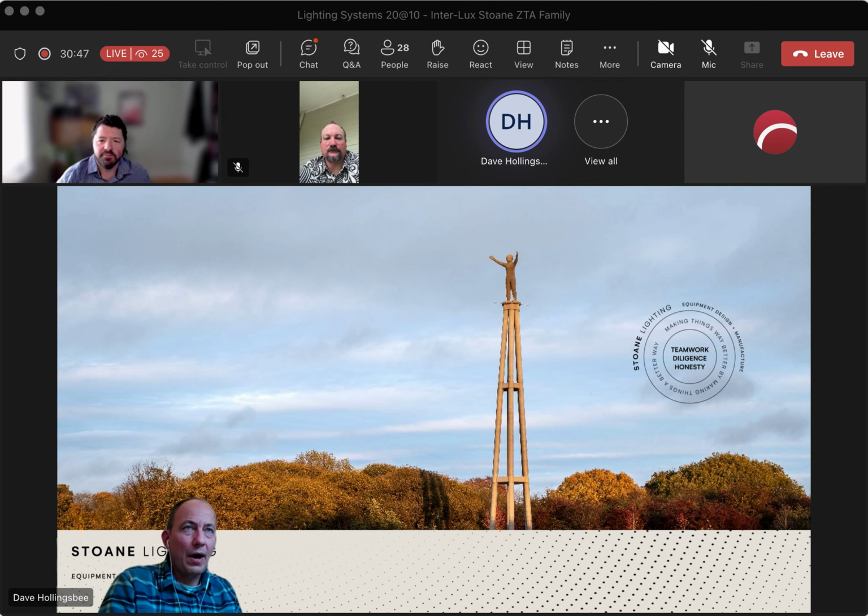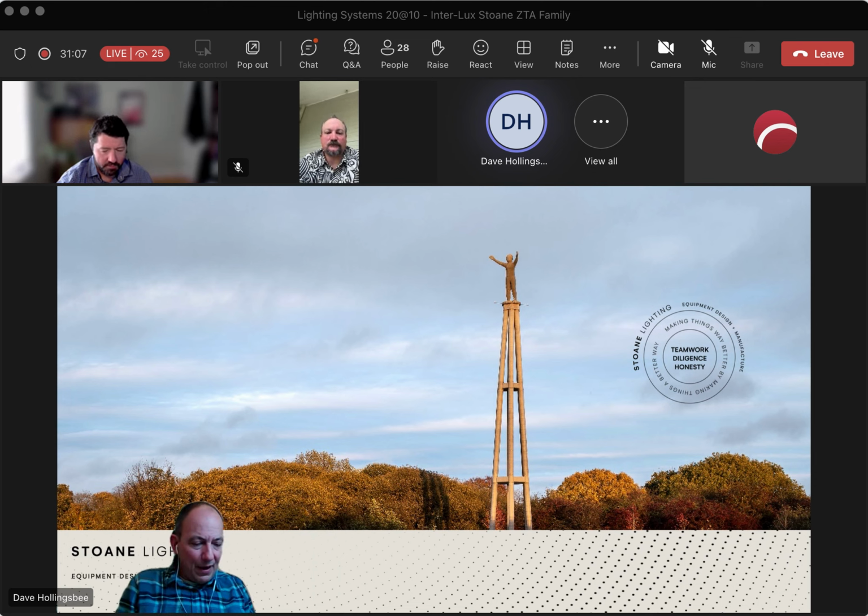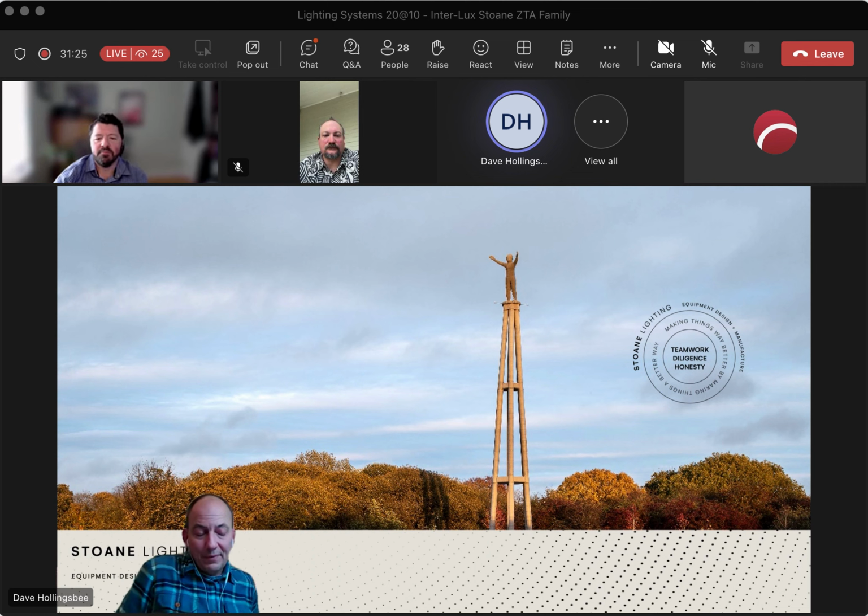The bit to watch out for when you're talking wired control is the data busing. It's just 2 bits of copper, but they're trying, I think it's Stucchi, they bought Eutrac, the one-track system, and trying to harmonize that. Whilst a lot of the 3-circuit track systems that are fairly common in Europe and the States are common for the energy, the main supply, the data busing is different in nearly every situation, so there's not commonality there. It's normally surmountable, but you have to pair up the track adapter with whatever track's on site, so we've come close to getting burned by that on site. But as long as you're wary, lots and lots of options.